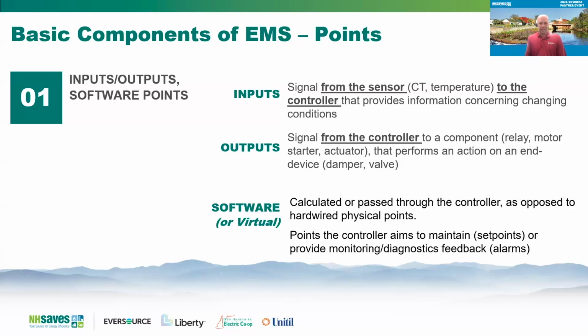It is a status that's typically a CT around the wire that measures current, and it tells the control system that, yes, this fan is either on or off, as opposed to a fan speed, which is oftentimes an output from the control system. It's telling the fan to go at a certain speed. Now, that doesn't mean that that's the actual speed the fan is at.